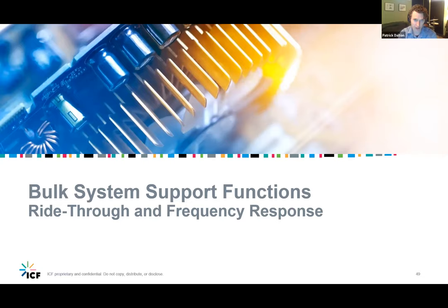And I think that as a practical matter, I mentioned how messy distribution systems can be. We do, unfortunately, often accept brief periods of time of low or high voltage, especially during emergency conditions. And there is a wider range of voltage within that standard I've been mentioning. ANSI C84.1 has this range B that extends beyond the normal voltage range, and that is to allow for some of these abnormal and emergency conditions. So it certainly is possible. It's something we don't like to see, but the volt watt helps, but it won't necessarily alleviate the condition entirely. So that's a keen observation someone made out there.